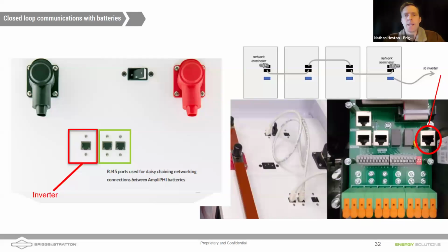Quickly showing here, Daniel, this is a SimpliPHI battery, and we're showing how you would wire that. Communications wiring is key. You're daisy chaining your batteries. One thing I'll point out with this one is you need to have terminating resistors and open ports on a CAN bus. Those tell the communication along the CAN bus, hey, this is the end of the chain, no more batteries to my left, right? And so make sure to have those terminating resistors.